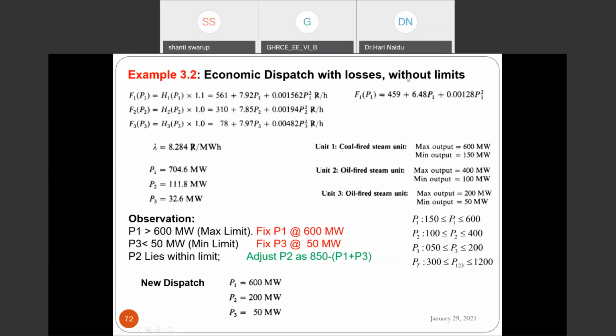Sorry, it is with limits, not without limits. P1 should lie between 150 and 600. P2 should lie between 100 and 400. P3 should lie between 50 and 200. The total generation should lie between 300 and 1200. You see here, P1 is 704, which is greater than 600 megawatts.